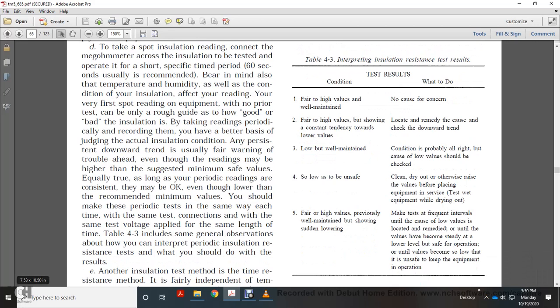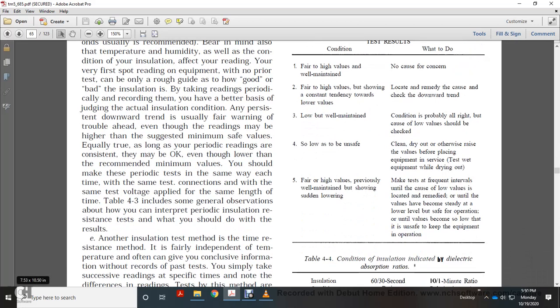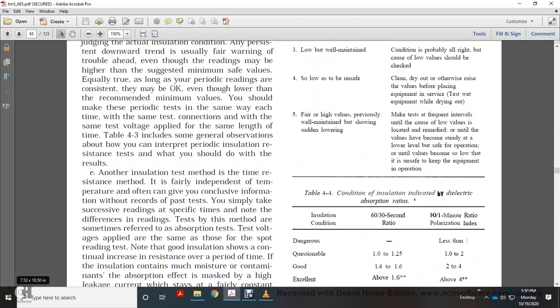Fourth, we include the general observations about how you can interpret the periodic resistance readings, what you should do with the result, and another insulation test method. The time resistance method is fairly independent of temperature, but often gives you conclusive information without the record of past tests. Simply take successive readings at specific times and note the difference. Tests by this method are sometimes referred to as absorption tests, with voltage applied the same as for the spot reading test.